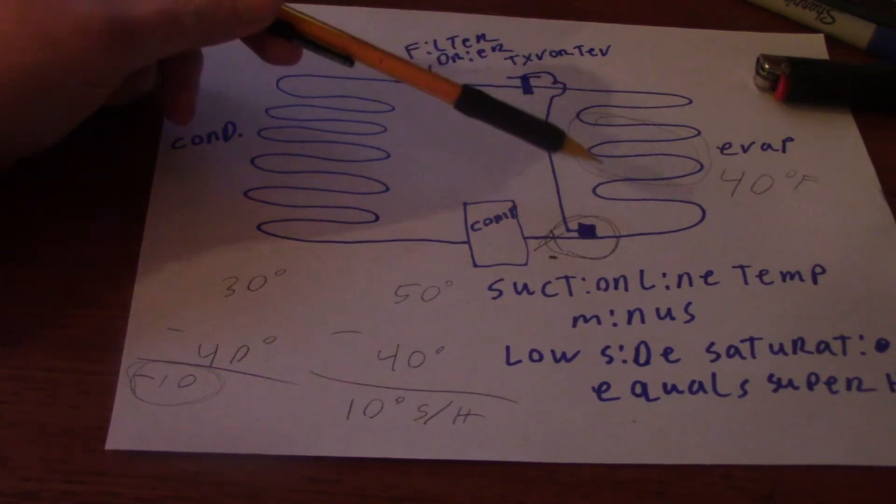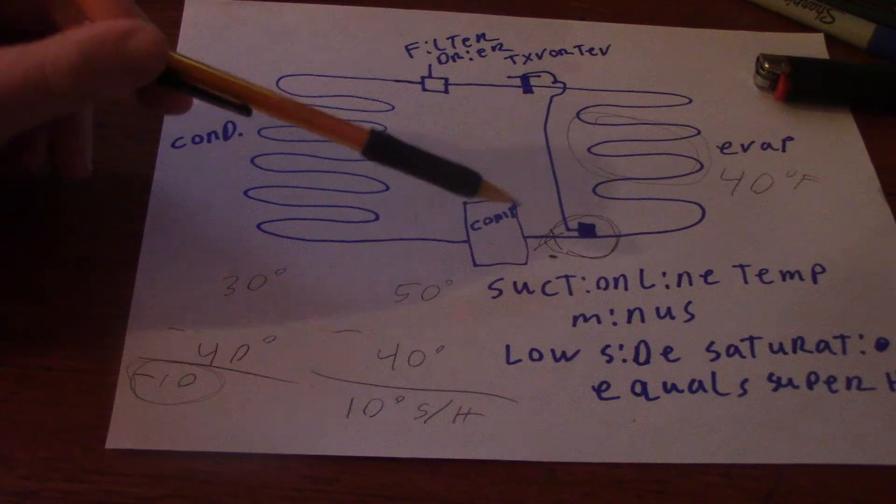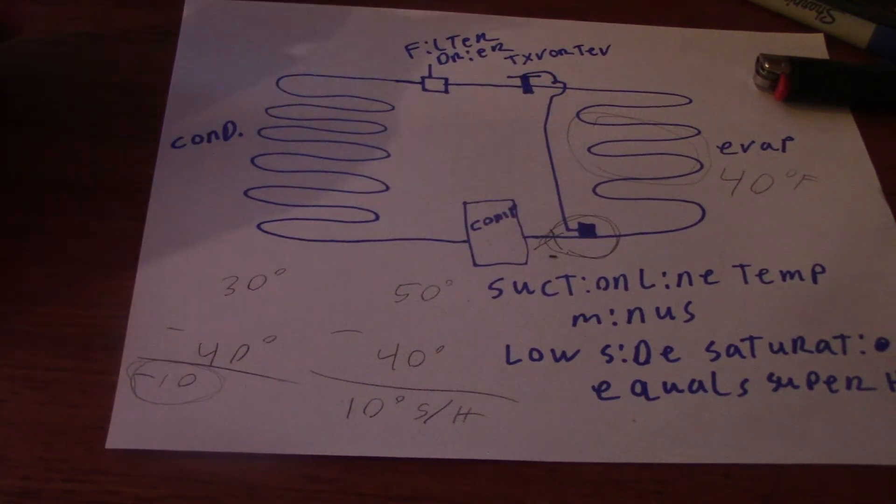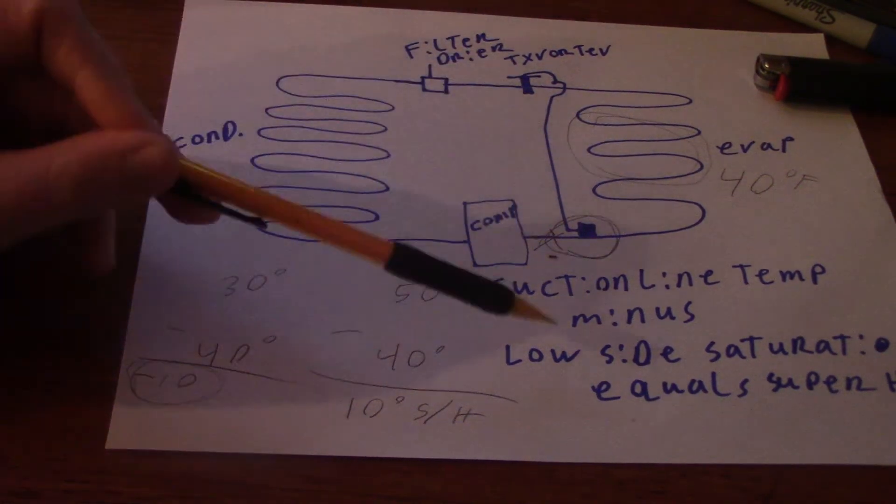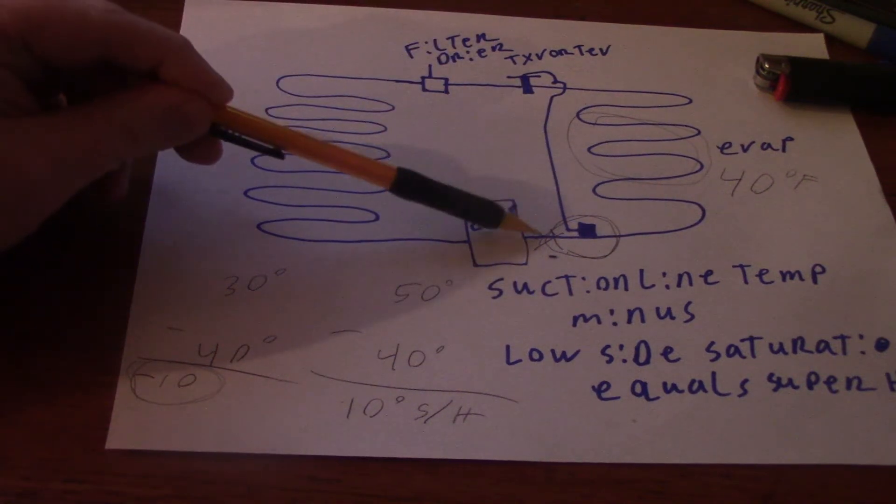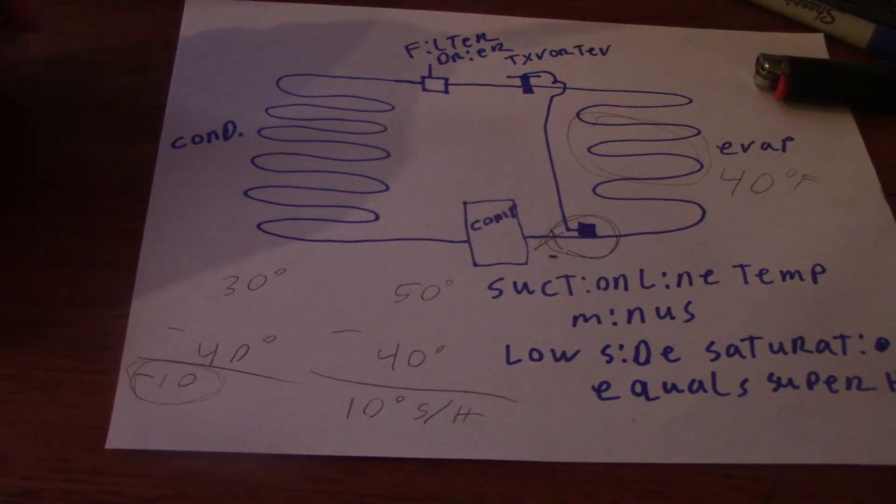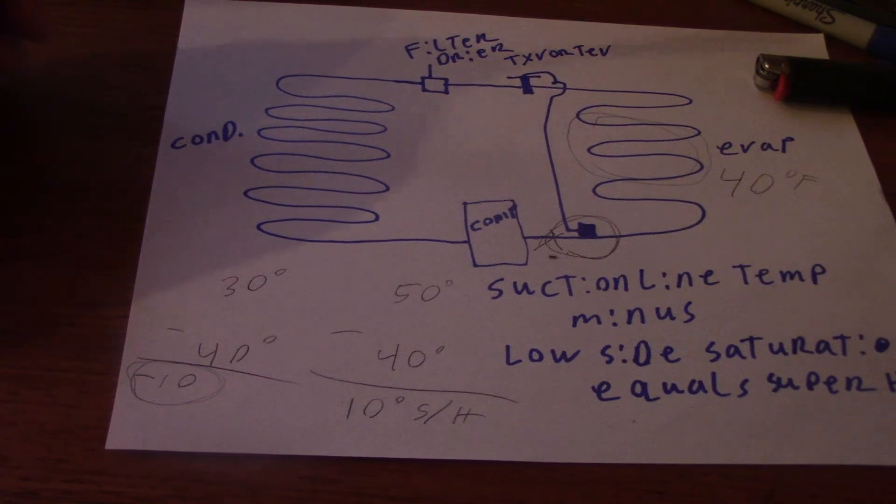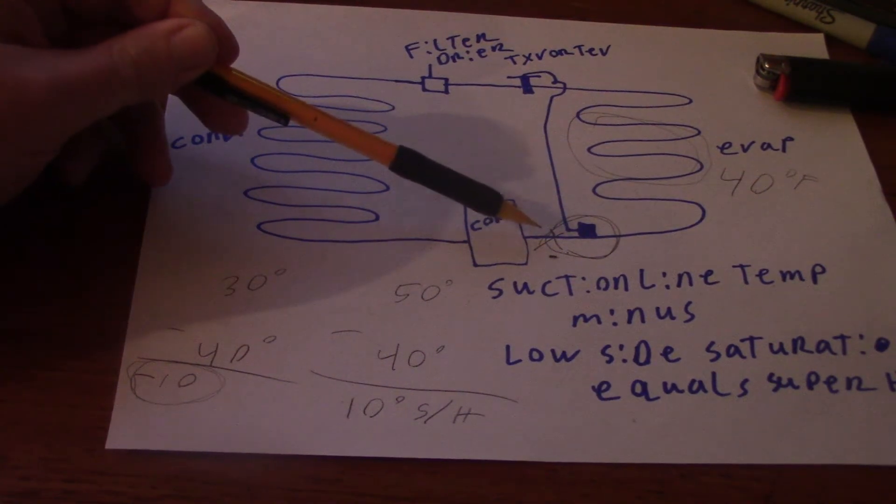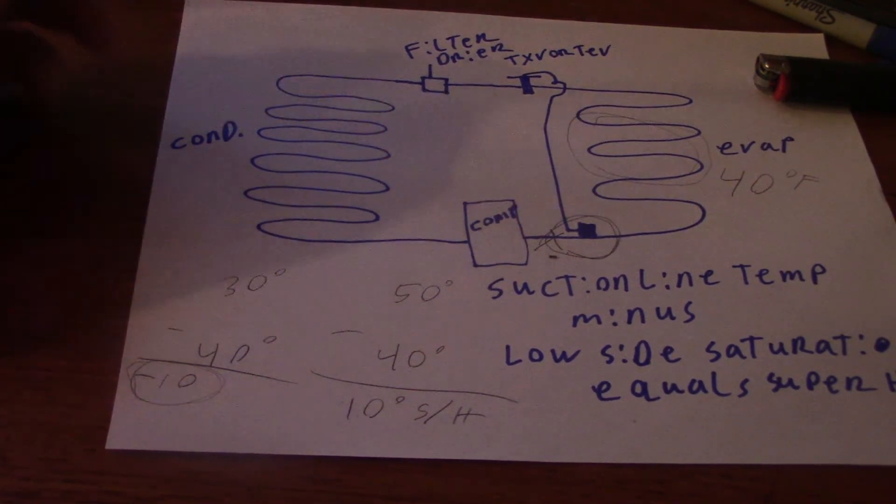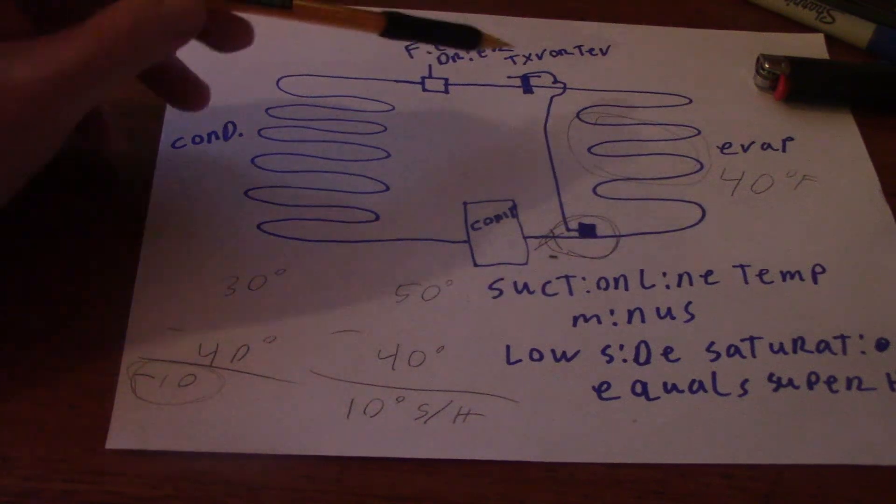If you had, let's say, a superheat of 5 right there, you could have a grossly overcharged system, hence the low superheat. If the superheat right here was, let's say, 30 degrees, you would have too high of superheat, and that would mean you're either undercharged, or you have a big load on the evaporator.